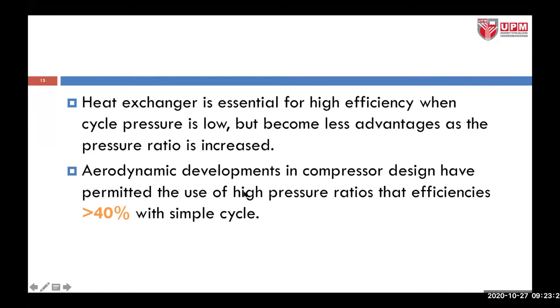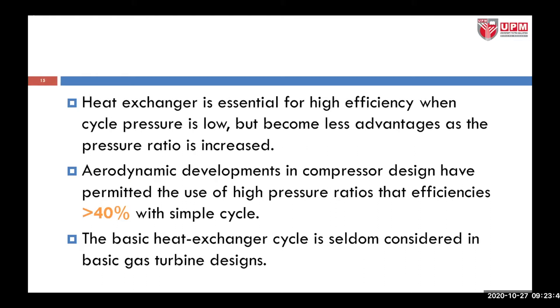Comparing figure 1.1 — a simple gas turbine cycle — to figure 1.4, with advanced aerodynamic development in compressor design in terms of different blade angles and numbers of blades, the compressor ratio can be increased and the overall performance of the gas turbine engine can be increased by 40%. The basic heat exchanger cycle is seldom considered in a basic gas turbine design because, even though the efficiency can be increased by 40%, the power output is reduced by 10%, making the advantage quite small compared to the weight penalty and other related costs.